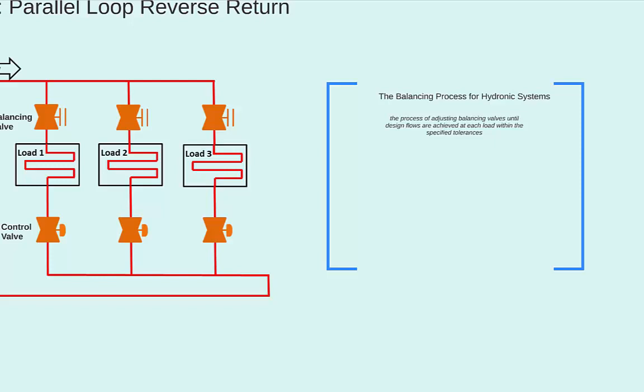The balancing process is done by running the pump at full speed and keeping all the various control valves wide open. It is an iterative process because if you adjust the position of a balancing valve at load 1, it changes the flow through all other coils. So the TAB team might have to adjust the balancing valve at load 1, then at load 2, then at 3, and then redo the whole sequence several times until they get all the flows to within the specified tolerance. For example, plus or minus 5% of design flow.